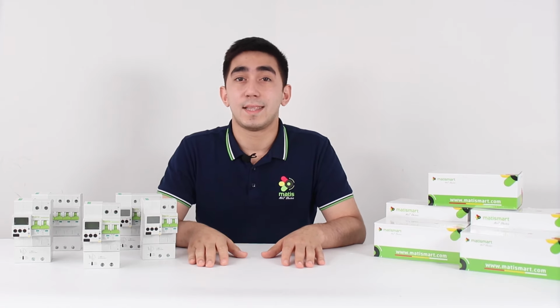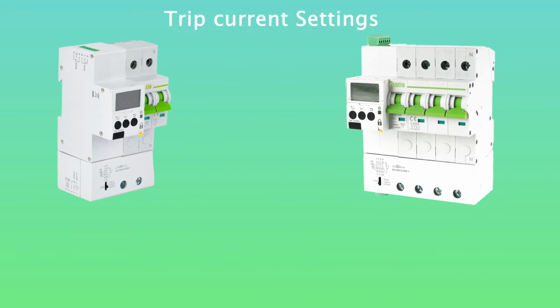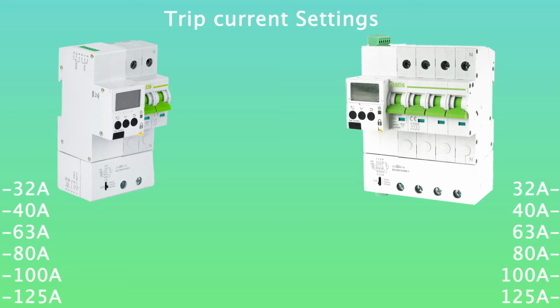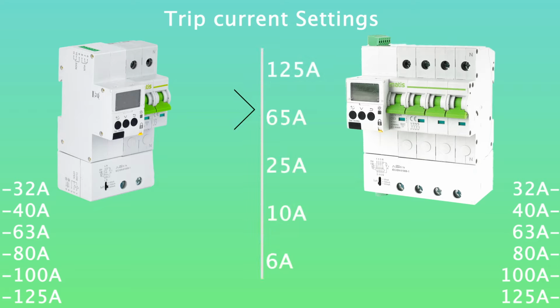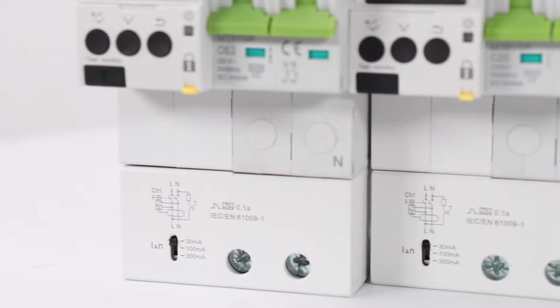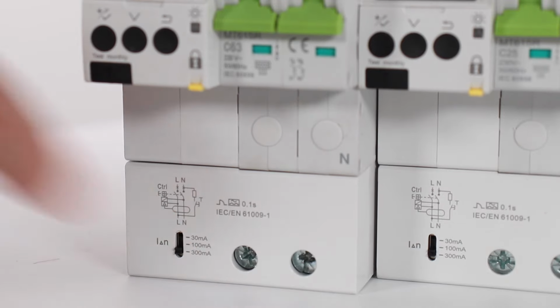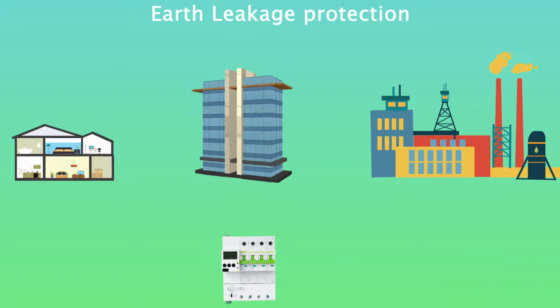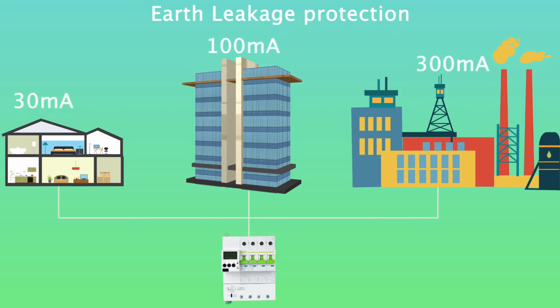I want to note that this device has several types of rated shutdown current. Those that you can buy are visible now on the screen. But it is worth noting that, as in the case of the MTS3, you can change the nominal cutoff threshold from 6 amps to 125 amps. Such a possibility of adjustment is also available with the sensitivity of the residual current. Right on the device you can choose the sensitivity in the range of 30, 100 and 300 mA, which gives the device a tolerance for operation in a complex electrical environment.